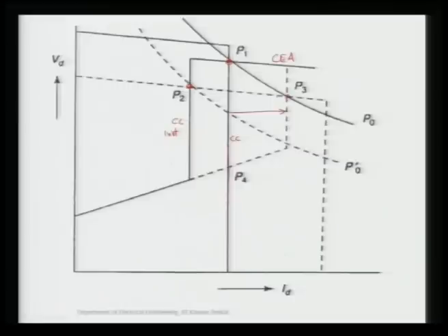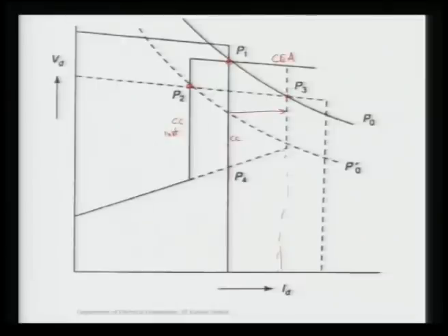So, what happens is, it is better that we increase this characteristic, the current order here, to get the same power. This is the new current and this will be our operating point. So, if the power has gone down, then we try to increase the current order CC setting, that is the ID which was the reference, so that we can maintain the same power.